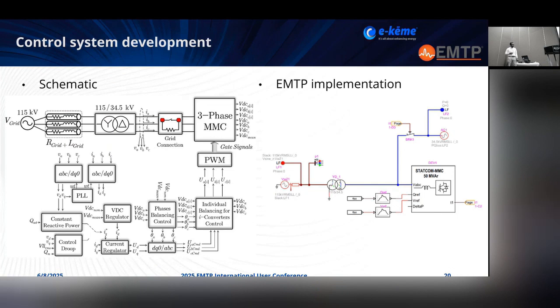Next, please. In this slide, we show the proposed state control. We can see the outer loop, the constant reactive power, and the next inner loops, the DC voltage regulator and phase balancing control, and finally the individual balancing for the currents of the converters, sorry, of each converter. And it's important to mention that the whole system is simulated in EMTP, and all elements are constructed based on native or original library models in the software. Next, please.